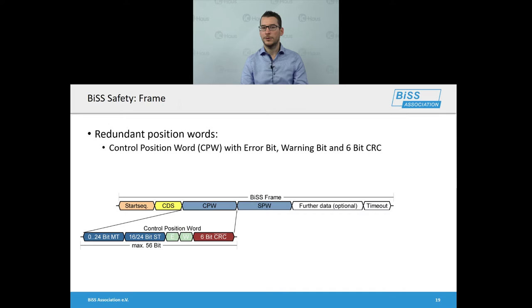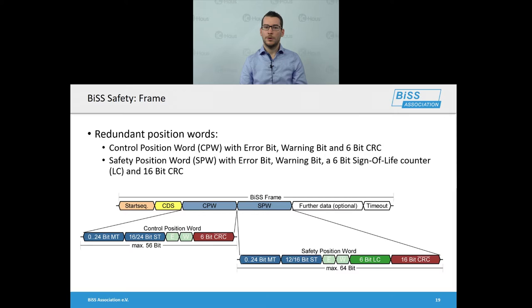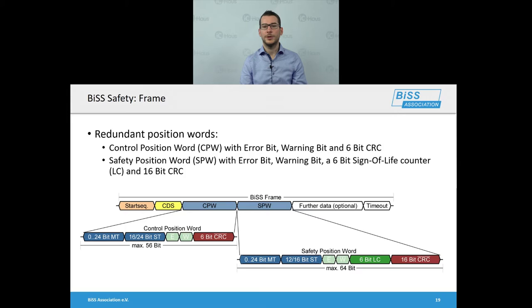The control position word consists of multi-turn and single-turn information for a rotary encoder, or linear information for a linear encoder. It includes an error bit and a warning bit, and the whole data content is protected by a 6-bit CRC. The safety position word also contains redundant position information — multi-turn and single-turn or linear — but usually at lower resolution since it is only used for safety checks. It includes the error bit, warning bit, and a 6-bit sign-of-life counter used to detect missing frames. The whole data content is protected by a particularly robust 16-bit CRC.